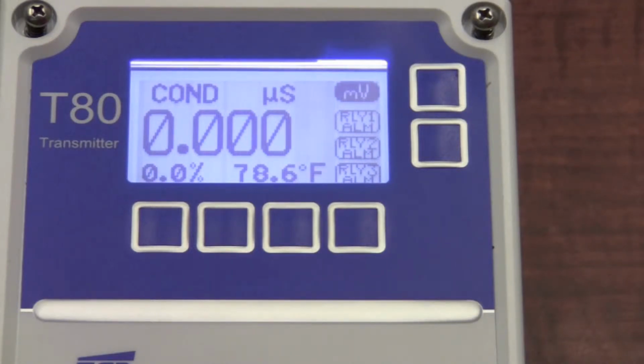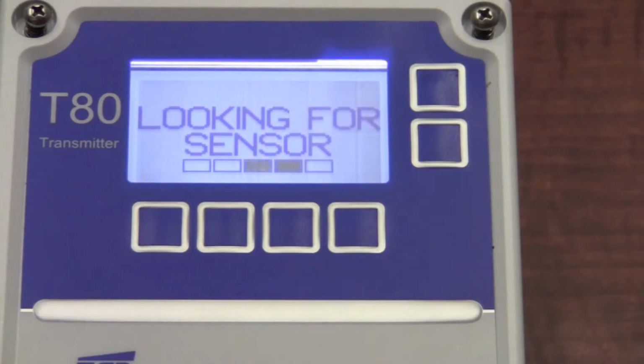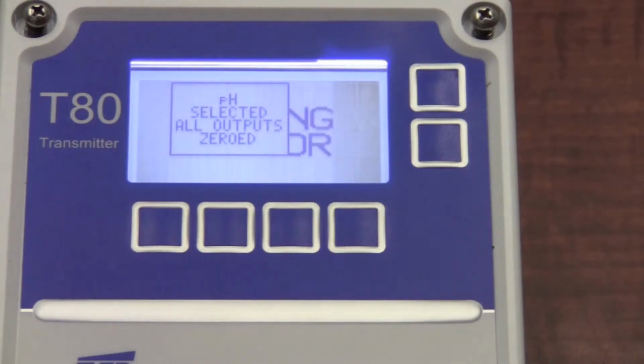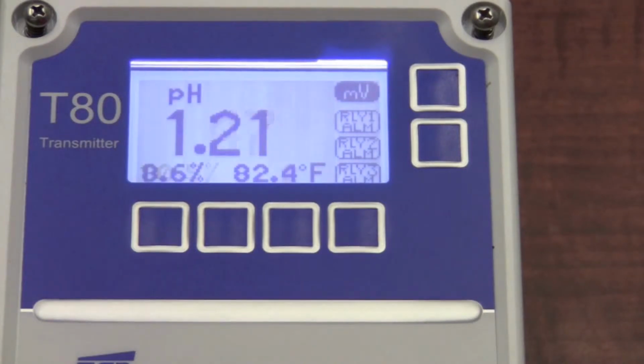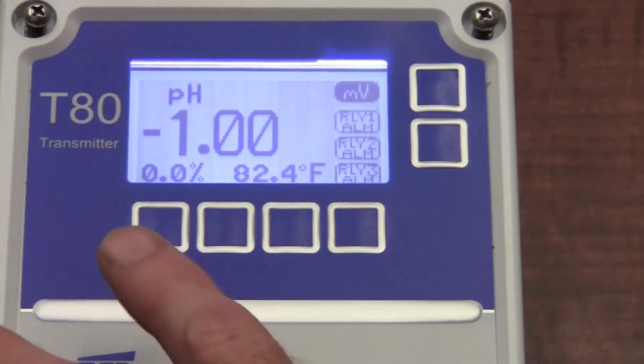I'm going to go ahead and disconnect the conductivity sensor and reconnect a pH. It interrogates the sensor and finds that it is a pH probe. Now, on the front of the display, I have 4 keys, and they become soft keys. Hitting any one of those keys twice in succession puts it into the configuration menu.